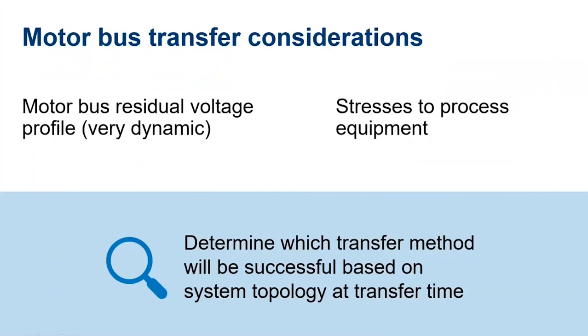And then this brings us to the fast transfer consideration. So what we need to know to do the fast transfer, we can do a detailed study of all the motors involved and all the loads involved in the bus, or we can have a good sample of the spin down of the motors. So we just disconnect the bus and we see for different load conditions that we would be interested in how the voltage goes down in frequency and voltage. And with that, we can get a good idea of how the bus transfer really will operate for each case.